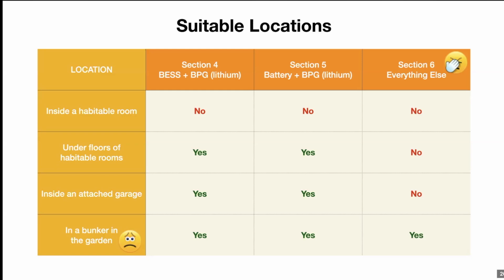I'll get to that. And you're talking about a ski lodge. Well, a ski lodge has definitely got habitable rooms within it. It may have some dedicated rooms that are not deemed to be habitable, such as a storeroom or a utility room. But one of the overriding principles of 5139 is that irrespective of which section you're in, sections 4, 5, or 6, if there is a habitable room adjacent to a battery system, whether it's a BESS or a battery system, you need protection against the spread of fire. So all those ski lodges with wooden walls, if there is a bedroom, a lounge, a kitchen, a bathroom behind that wall, you're going to have to put up a fire barrier.